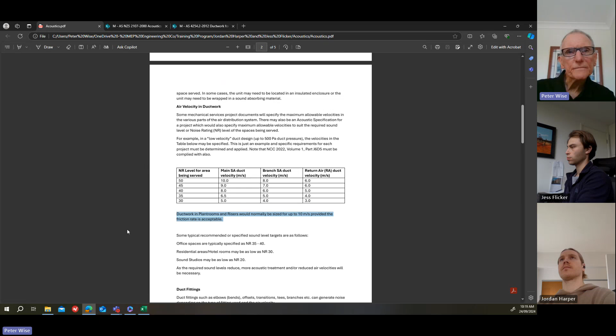Ductwork in plant rooms and risers would normally be sized for up to 10 meters a second, provided the friction rate is acceptable. So again, that's the NCC. You've got to comply with the requirements there, which is 1 Pascal per meter in the index run. You'll find that as the velocities increase, the ductwork is getting bigger. Usually, if in a riser or a plant room, the duct is bigger. Achieving 1 Pascal per meter is not usually a major problem.